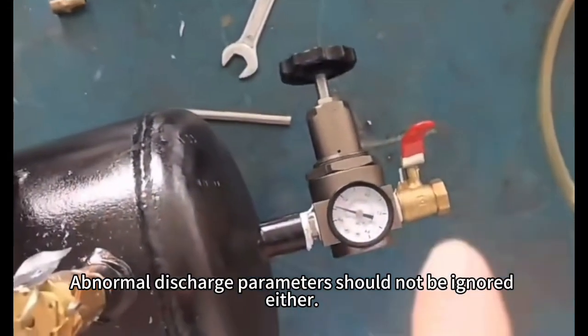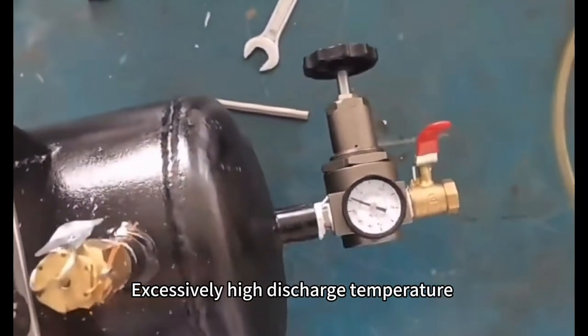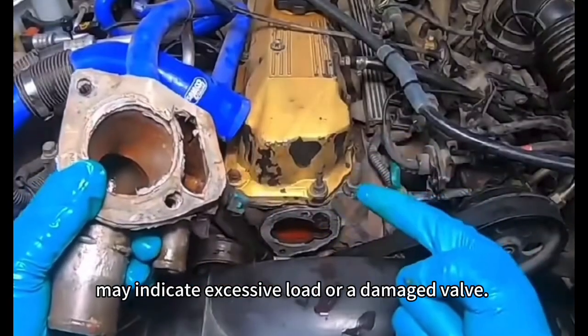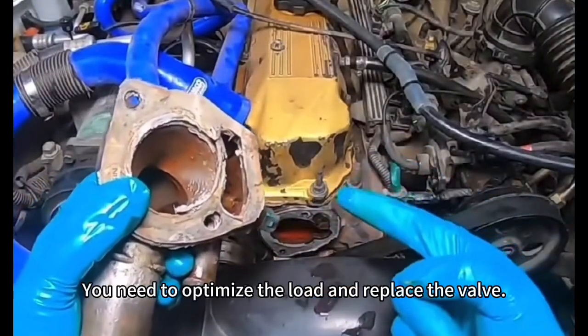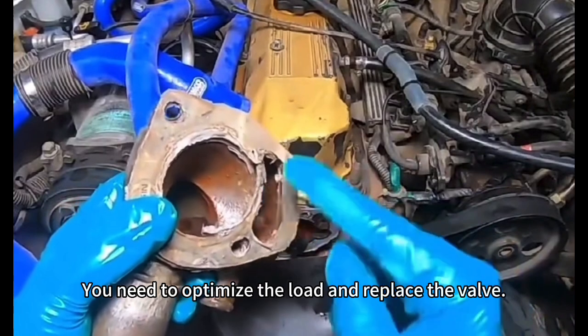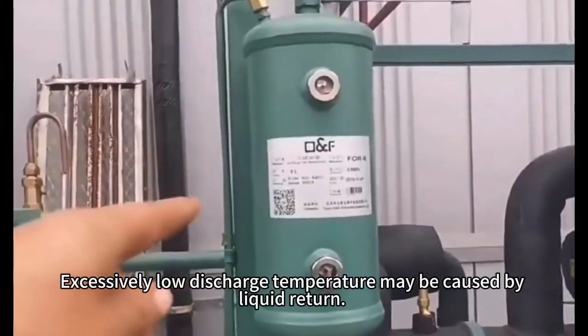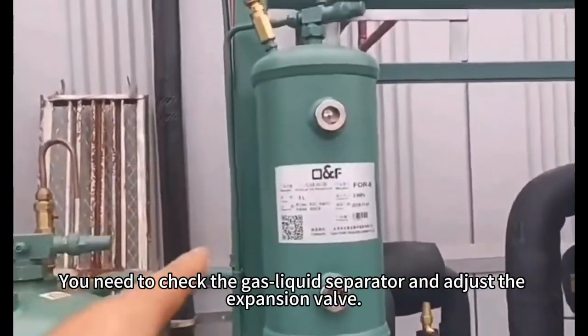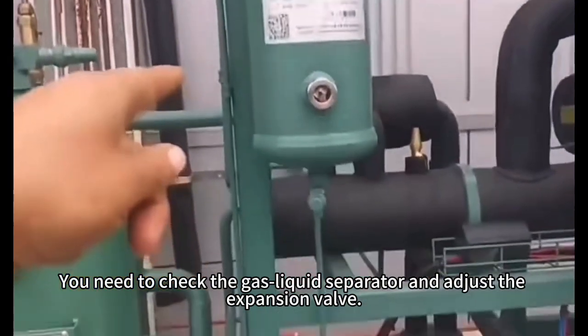Abnormal discharge parameters should not be ignored either. Excessively high discharge temperature may indicate excessive load or a damaged valve. You need to optimize the load and replace the valve. Excessively low discharge temperature may be caused by liquid return. You need to check the gas-liquid separator and adjust the expansion valve.